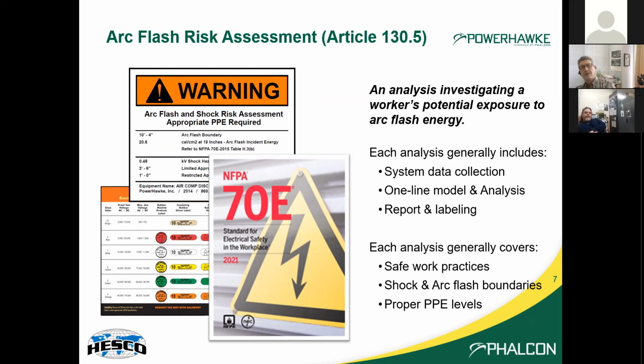It really entails collecting data on your system—probably 50% of the cost, mostly for existing installed systems—having crews like ours go out, wear the proper PPE, open up the equipment, and catalog and detail every part and piece of equipment: how long it is, what size it is, manufacturer, style, type, model—all on the way to developing a one-line analysis model. Ultimately that analysis model is used to develop the labeling that ends up on the equipment.